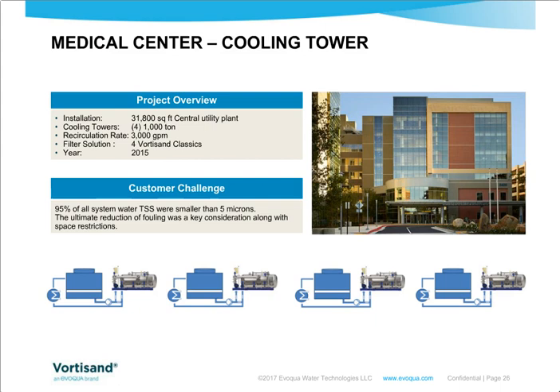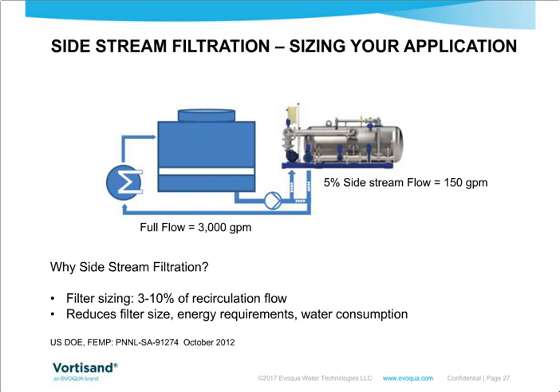Currently they were using centrifugal filters. And what happened was that we installed 4 different fine filtration VortiSand filters, one filter per cooling tower, as you can see here. And then we installed it on the side stream. This is important to note, as side stream filtration is becoming more and more the norm in dealing with filtration technologies. Why side stream filtration? It enables you to reduce the filter size and, more specifically, the cost associated with that filtration technology, that capital investment. So here's a cooling tower, as this illustration shows, with a full flow or recirculation flow of 3,000 GPM.